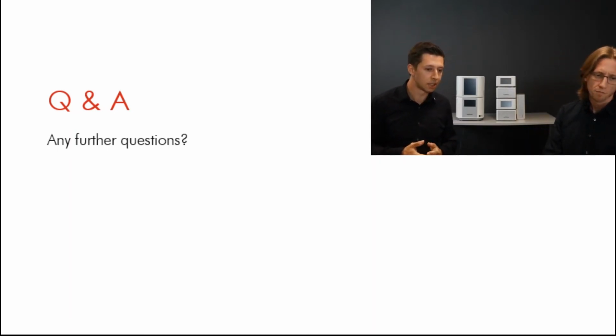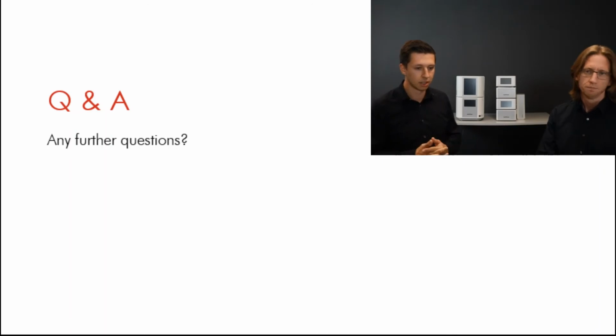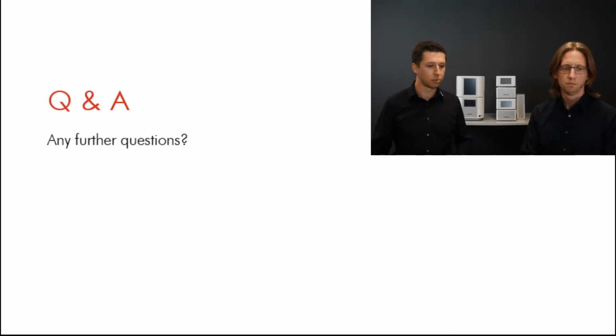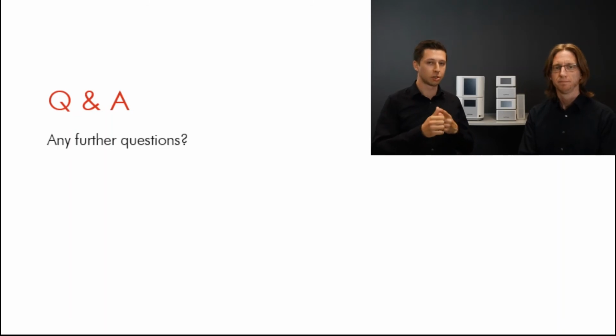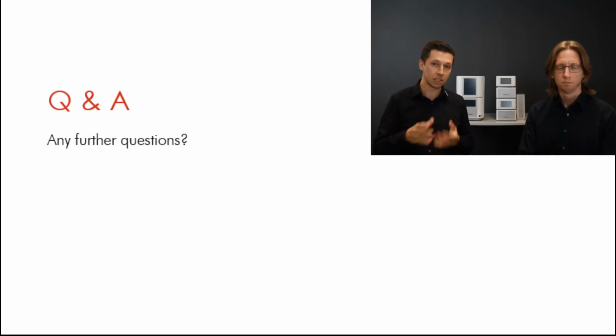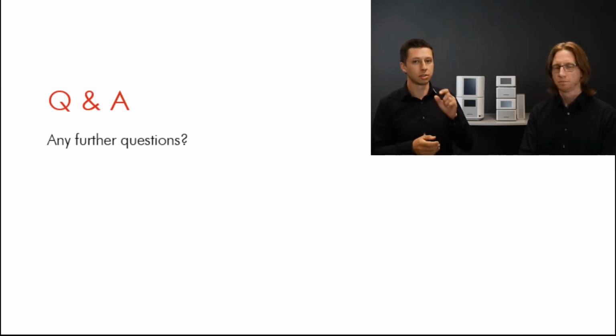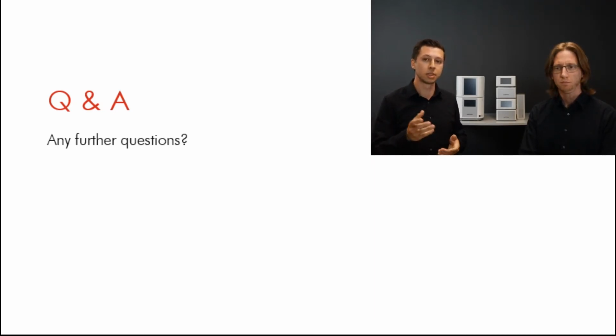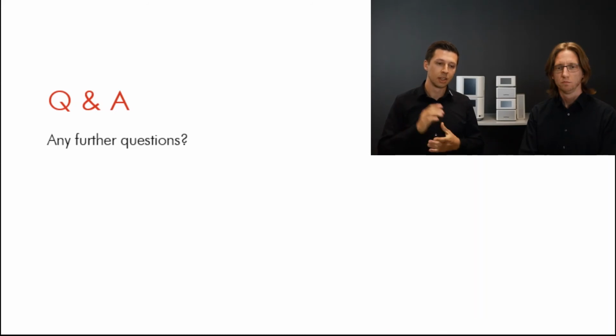And I can also see Gabriele wants to improve stray light and asked if you can do it with the advanced calibration and check that there's no dust on the optics. Yeah. So checking that there's no dust on the optics, perfect. You check, of course, first stray light in the safety glass if it's clean, and you check then by carefully looking into it if the lens is also clean.